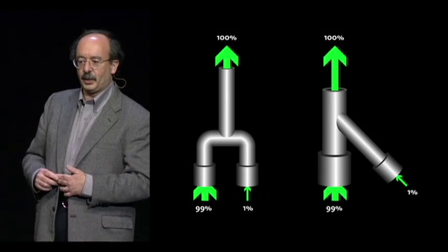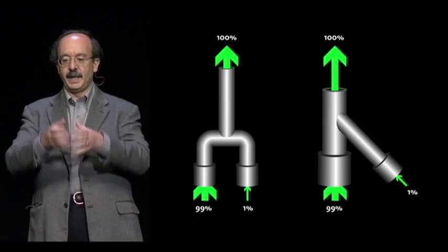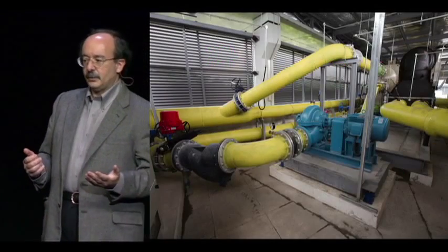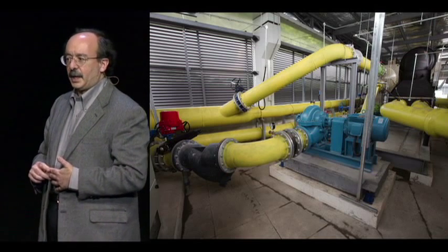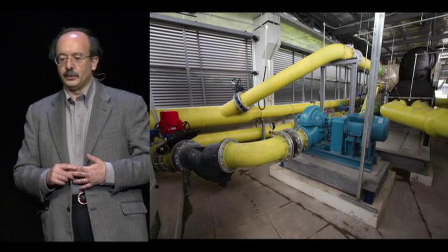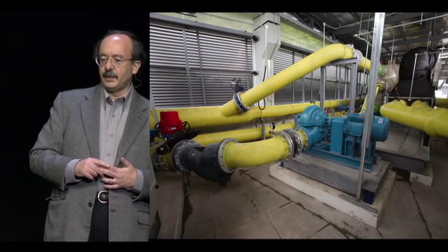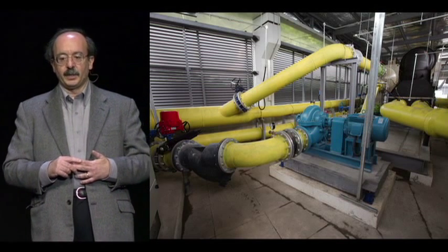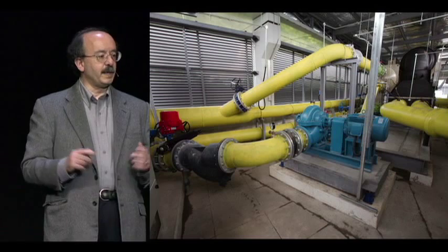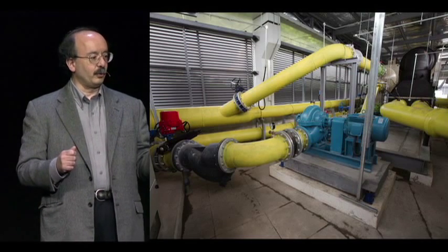And the same logic applies also with identical pumps in tandem. Here's a lovely example from the master designer Lee Eng Lock in Singapore, who is saving here 75% or 80% of the pumping energy, but it costs less to build, partly because it makes the pumps, motors, inverters, and electricals a lot smaller. So what does that mean for the electricity that's 60% used in motors?